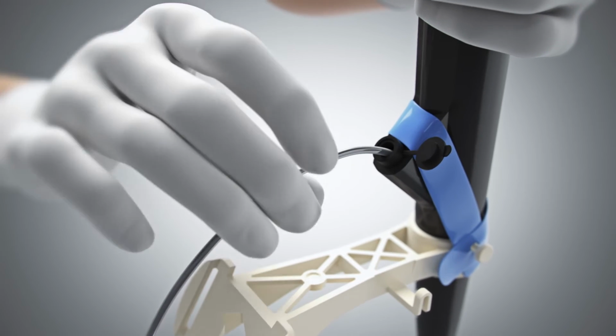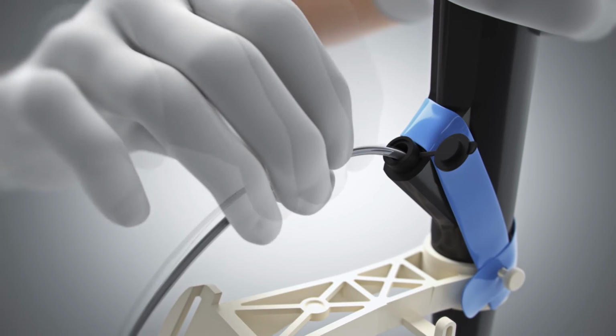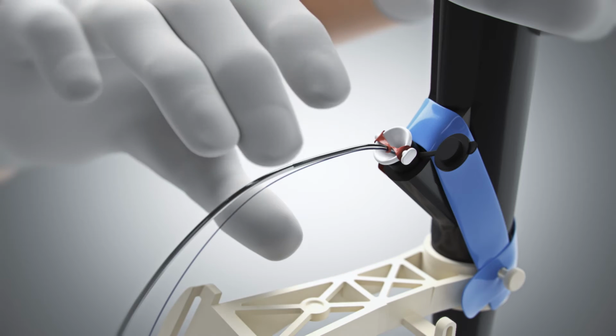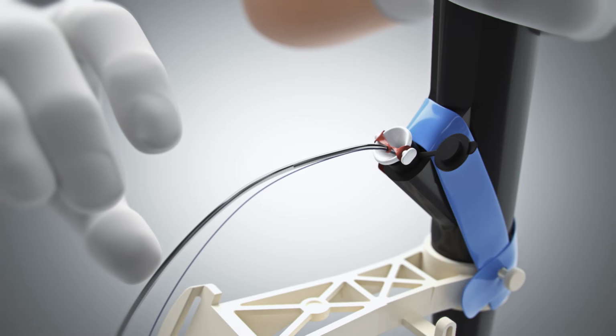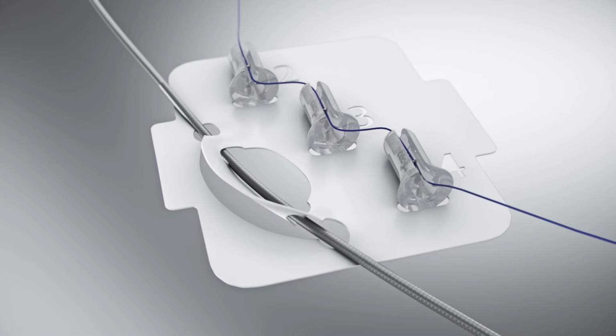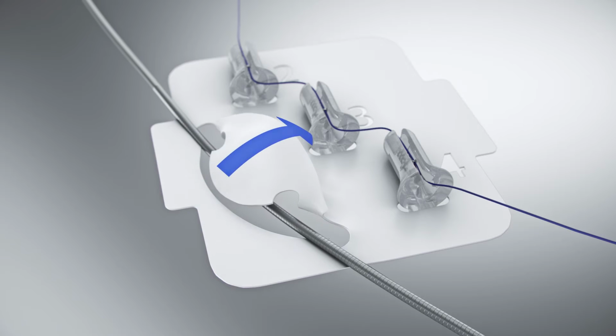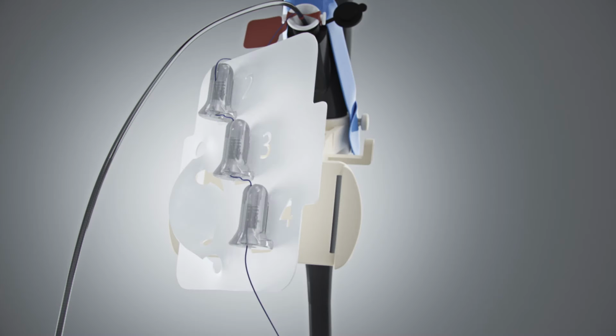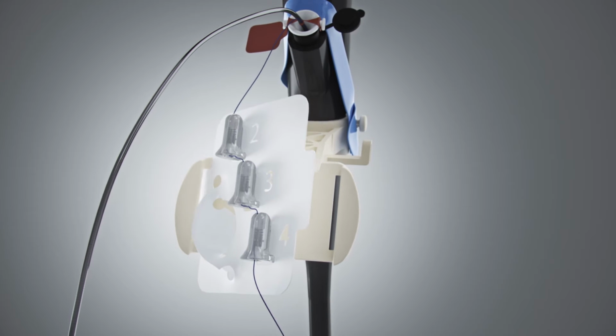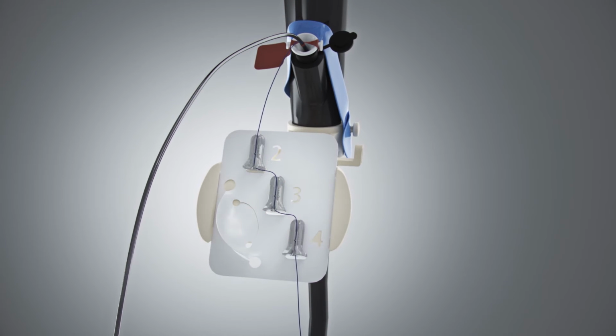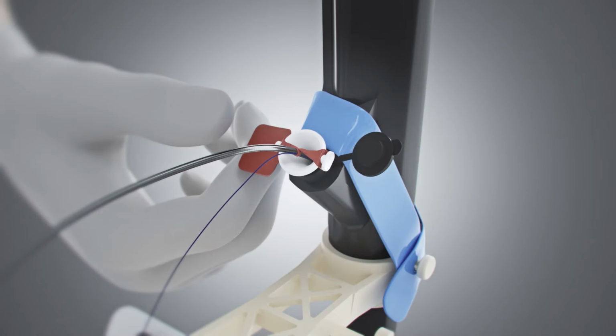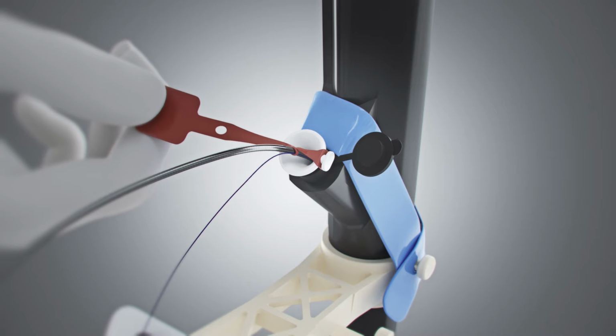Ensure the biopsy cap is open and the scope is straight. Fully seat the scope liner funnel into the biopsy cap. Remove the X-Tack backer card from the device catheter by folding the tab towards the helix tacks. Position the backer card with the number 2 proximal and attach by inserting both side tabs. Pull on the red scope liner clamp to release.